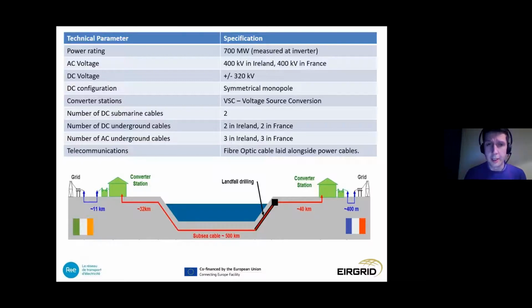In Ireland, our largest single infeed or outflow at the moment is that of the East-West Interconnector, or EWIC, which is 500 megawatts. And we undertook engineering studies on a range of factors, including the operational requirements and the characteristics of the Irish system, to determine what a suitable capacity level would be for the Celtic Interconnector. One of these would be the avoidance of large grid reinforcements or operational changes. And the studies concluded that 700 megawatts would be feasible without major investment to the existing transmission grid. And this was also confirmed through similar studies in France.